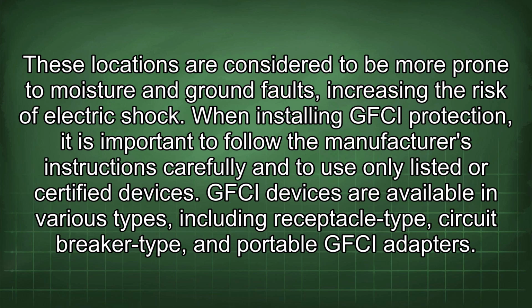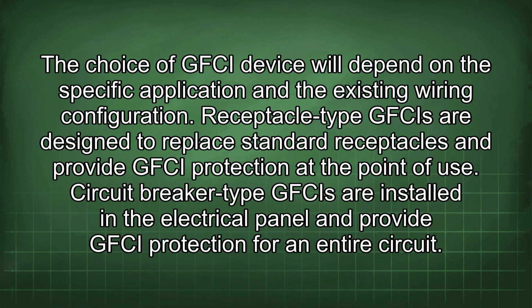When installing GFCI protection, it is important to follow the manufacturer's instructions carefully and to use only listed or certified devices. GFCI devices are available in various types, including receptacle type, circuit breaker type, and portable GFCI adapters. The choice of GFCI device will depend on the specific application and the existing wiring configuration.